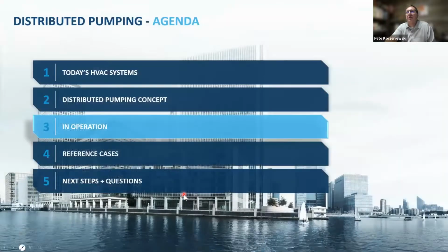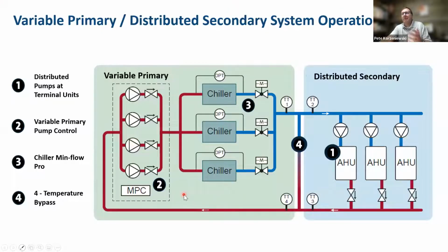All right, so if we look at those components and operations, we're going to talk about those similar areas. We'll talk about the distributed pumps and how to control them out at the loads, or out at the air handlers. We'll talk about our primary pump control, which will include chiller minimum flow protection, as well as 4 temperature bypass.